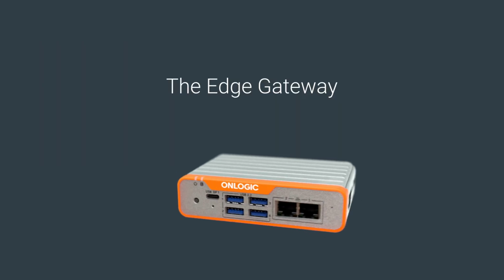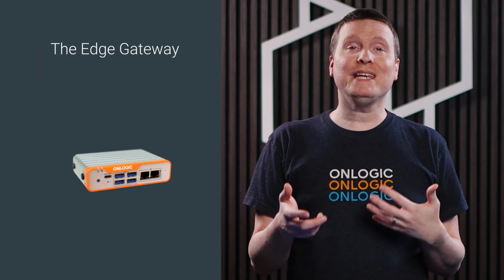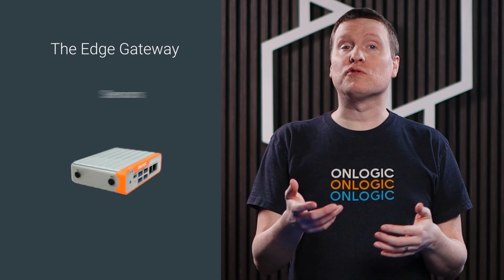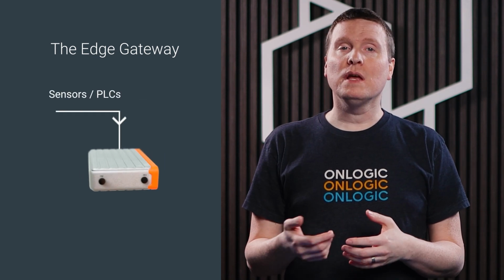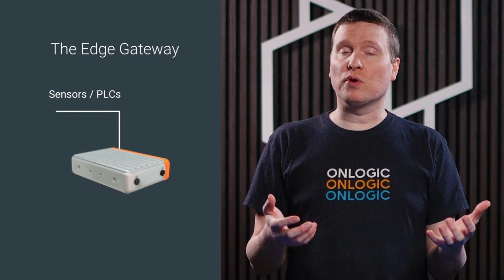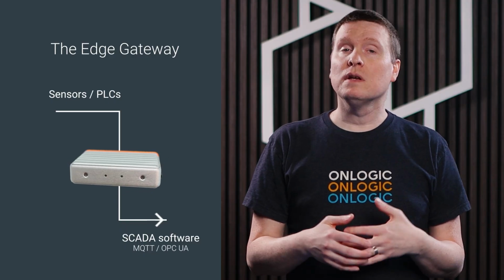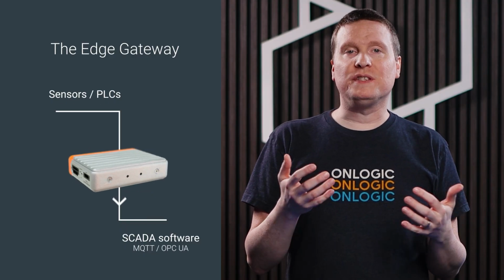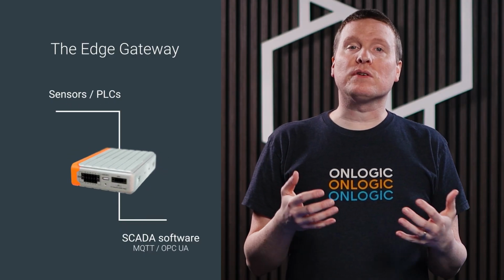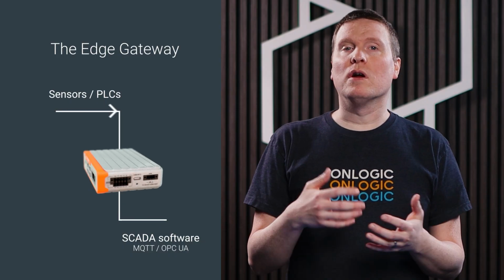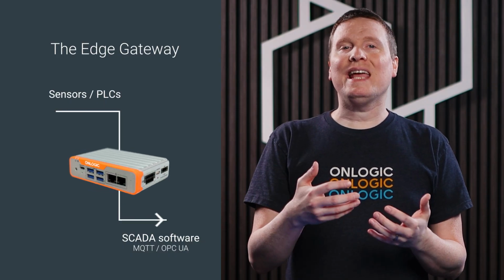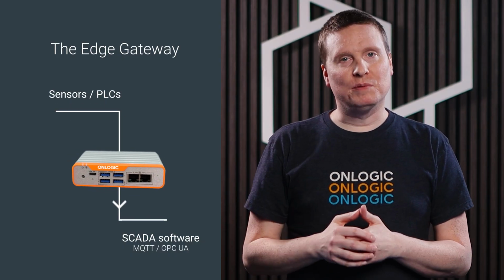The gateway is your boots on the ground. Its job is to live near the machinery, collect raw data from sensors or PLCs, and translate it into a communication protocol your SCADA software understands, like MQTT or OPC UA. Because these gateways are often tucked away in cabinets or mounted directly to machines, they may have to survive in suboptimal conditions for technology. Here are your key considerations for SCADA gateways.